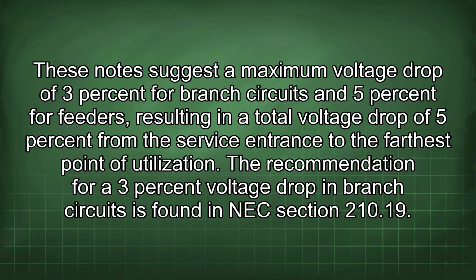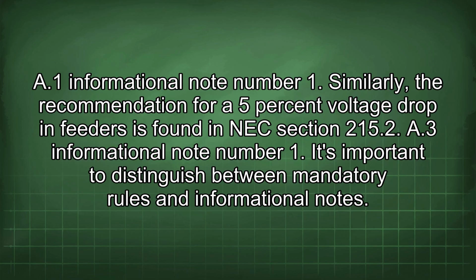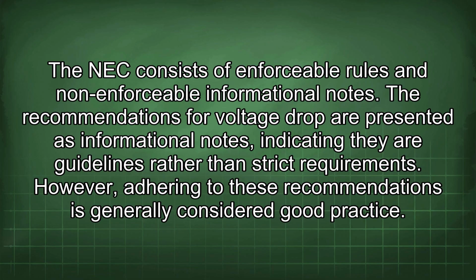The recommendation for a 3% voltage drop in branch circuits is found in NEC section 210.19(A)(1), Informational Note Number 1. Similarly, the recommendation for a 5% voltage drop in feeders is found in NEC section 215.2(A)(3), Informational Note Number 1. It's important to distinguish between mandatory rules and informational notes. The NEC consists of enforceable rules and non-enforceable informational notes. The recommendations for voltage drop are presented as informational notes, indicating they are guidelines rather than strict requirements. However, adhering to these recommendations is generally considered good practice.